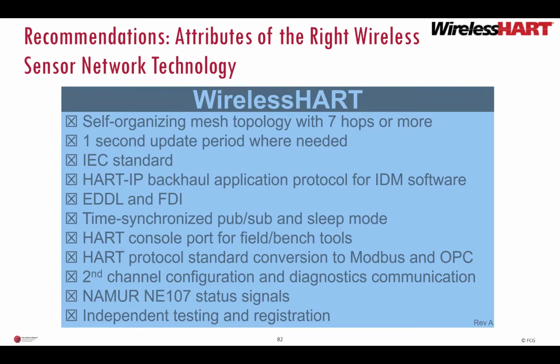Okay, to summarize. The recommendation is to use WirelessHART because WirelessHART has many features that make it the best wireless sensor network technology for plants. The self-organizing mesh topology with 7 hops or more, the HART console port, it's an IEC standard, the HART-IP backhaul application protocol for IDM software, EDDL and FDI, the time synchronized publish-subscribe communication and sleep mode, standard message and data formats converting to Modbus and OPC, plus client-server communication of sensor configuration and advanced diagnostics like vibration spectra. No other technology has all these features and therefore cannot achieve the same result as WirelessHART.